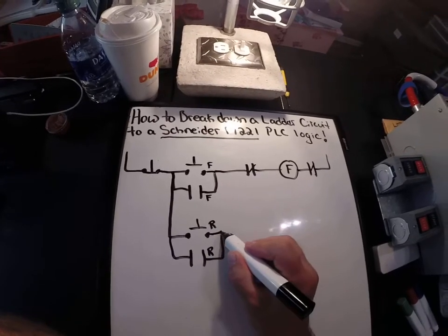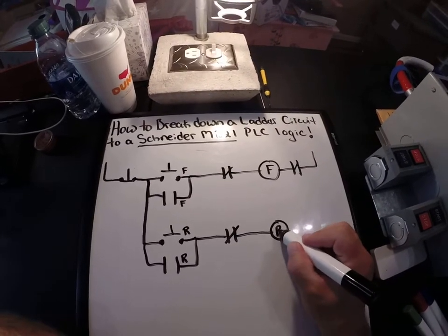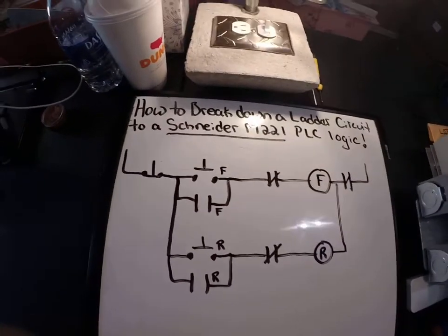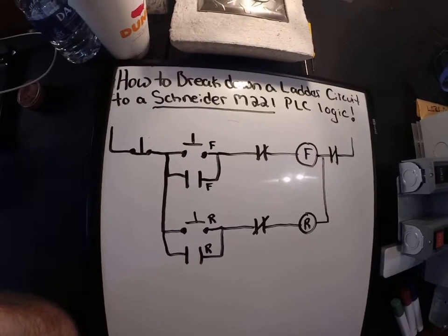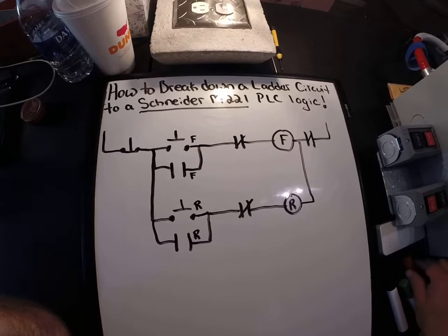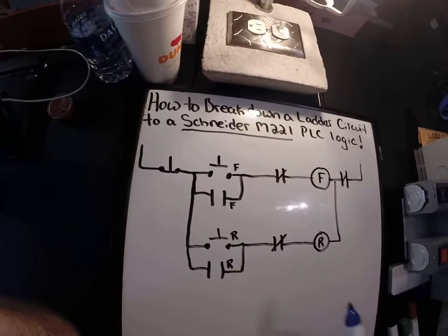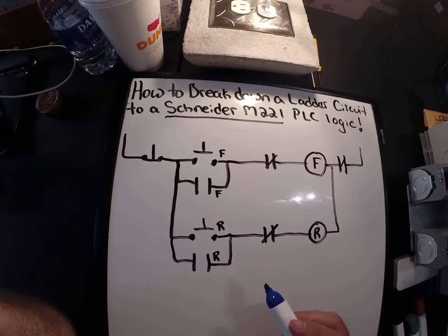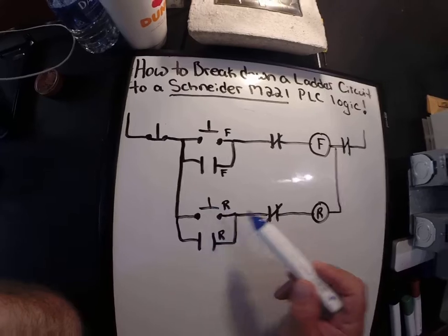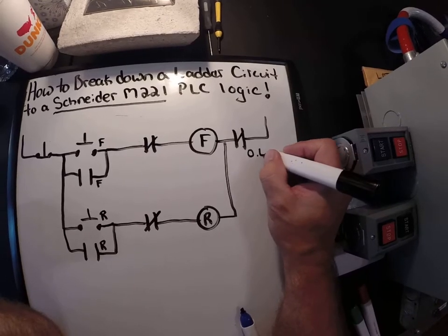After I get this drawn, we're going to methodically break it down piece by piece, input by input. So right now there's your basic drawing of how that should look in the circuit. So here's your motor logic, and then the students are like, well, what the heck do I do with this? First thing you've got to do is say to yourself, how many inputs do I have? We know switches and sensing devices are inputs. So I have 1, 2, 3, 4 inputs, because as you're aware, this is your overload.